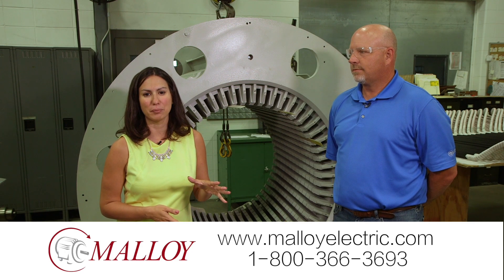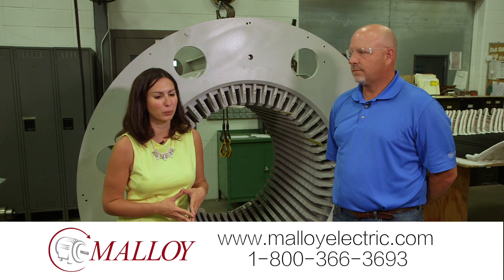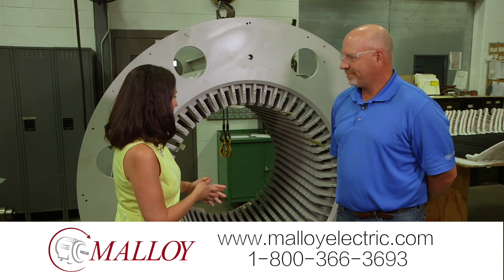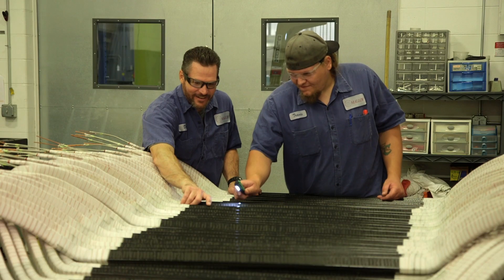We're inside the winding department at Malloy, taking a look at a pretty impressive repair job. I'm here with Randy, who's the plant manager, and one high voltage motor that they're working on. This is for a customer out of North Dakota — it came to them having failed with partial discharge, and they're in the process of winding it at this point in time.